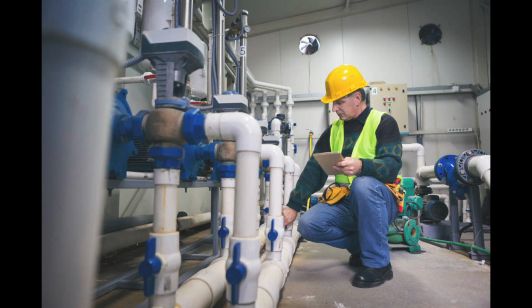So, preservation of marine boilers is a critical maintenance activity that ensures the safety, longevity, and efficiency of boiler systems on board ship. And lastly, commissioning and decommissioning are opposite but equally important processes in marine boiler operation. Commissioning ensures the boiler is properly tested, safely started, and ready to deliver efficient steam for shipboard use, while decommissioning ensures the boiler is safely shut down or cooled and prepared for inspection, maintenance, and layup.